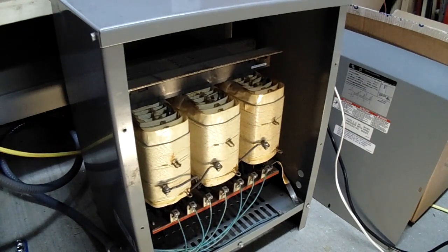Since the high side is in a delta configuration, that means each winding, each leg of that is rated for 460 to 480 volts, whatever you're putting into it up there. And the low voltage side is rated for 260 from the leg to ground, or 460 from leg to leg, or line to line, whatever you want to call it. So I want to configure the transformer in such a way that I can use it as a direct step-up or step-down transformer, with both high side and low side in a star configuration. So this video, I guess we'll call it how to wire a transformer into a star-star configuration.